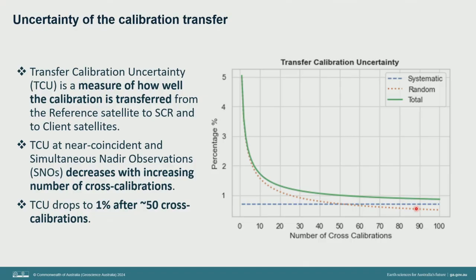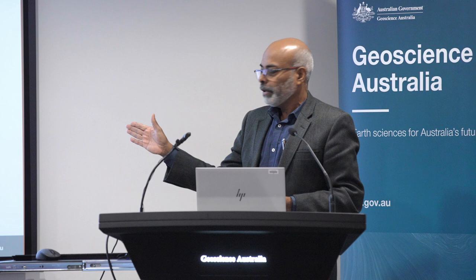In terms of transferring the calibration across, what is the uncertainty? This graph gives you an idea of the transfer calibration uncertainty, as we call it. It's a measure of how well the calibration is being transferred between the different systems. The green line is the total of the systematic and random components of uncertainty, and you see the percentage drops from about 5% to below 1% after 50 cross-calibration opportunities. So after about 50 cross-calibrations between the SCR and a target system, the uncertainty falls to well below 1%.